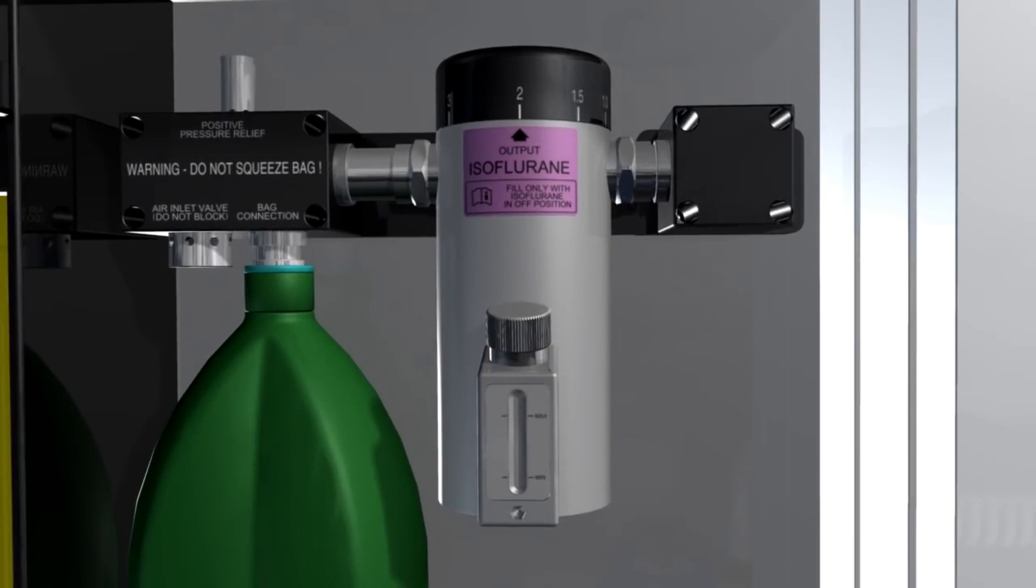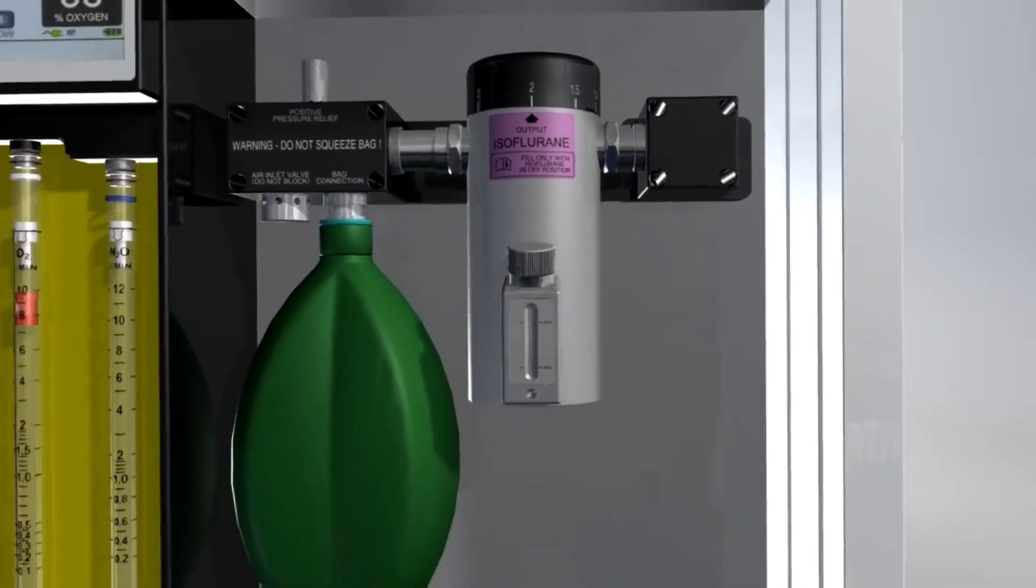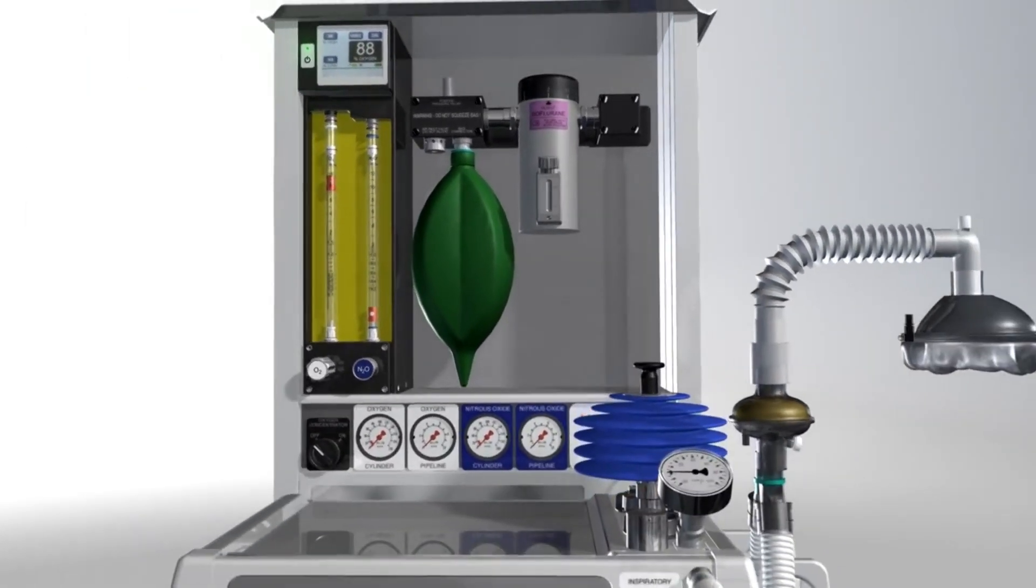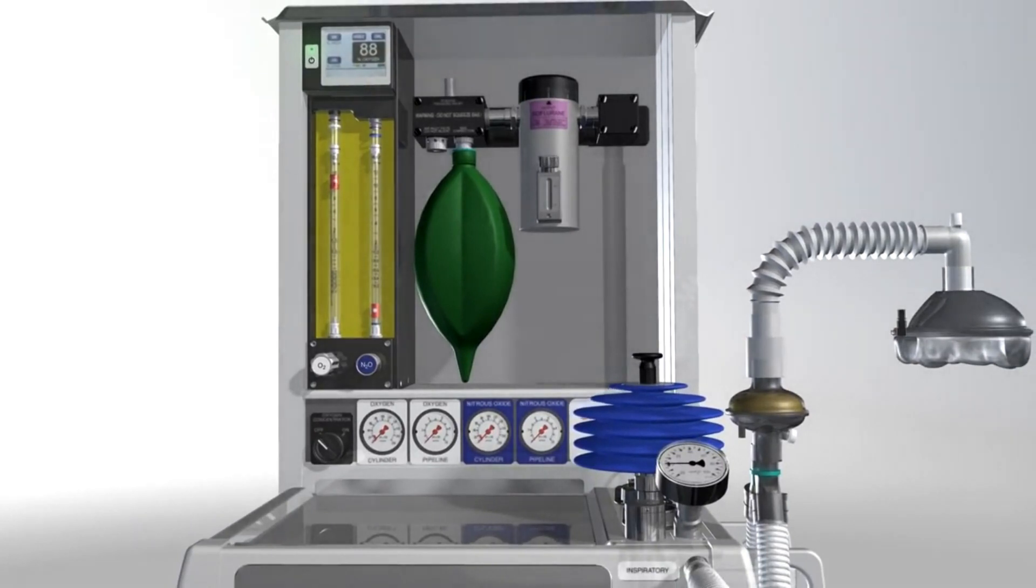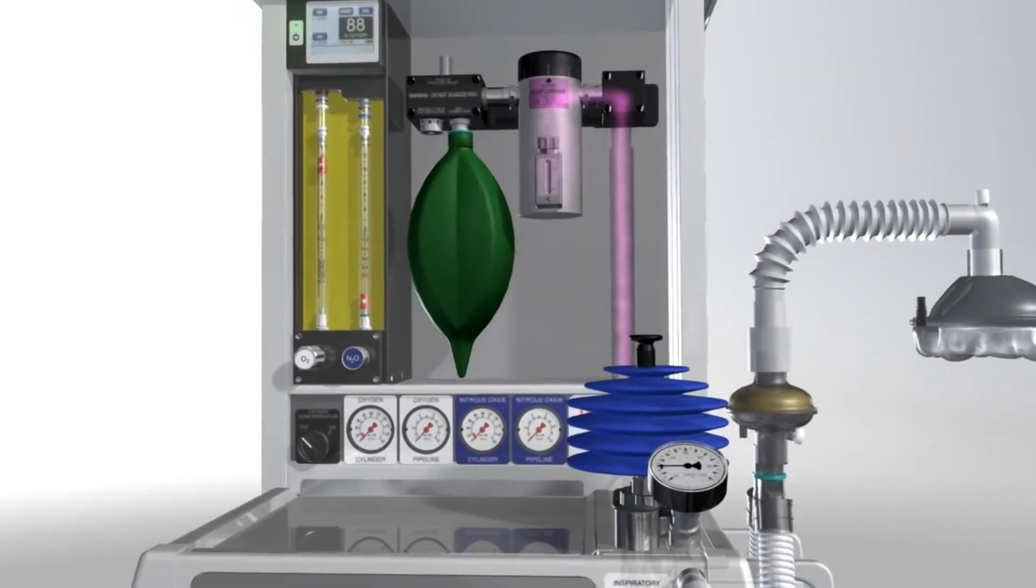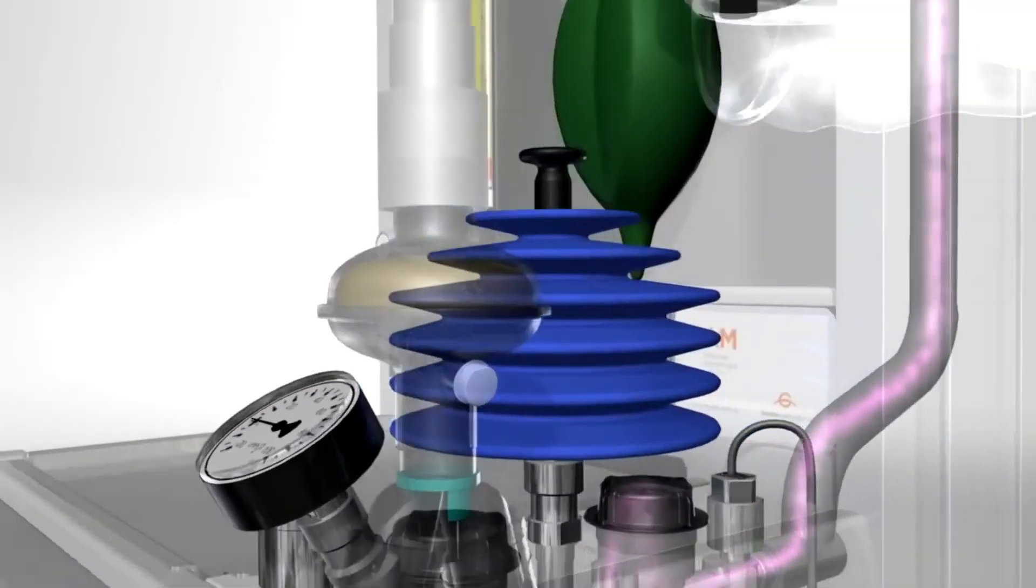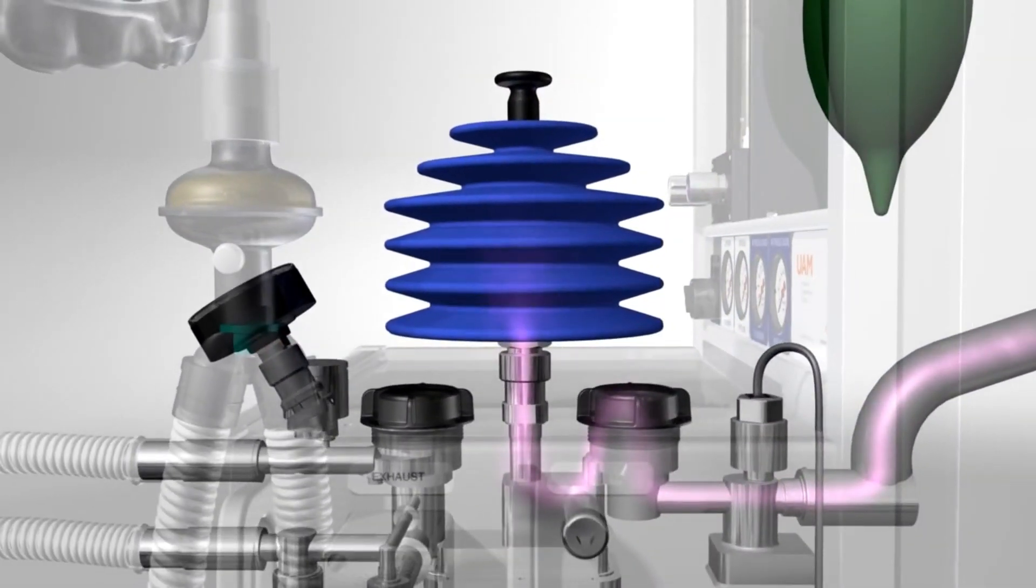The internal resistance of the vaporizer is usually high, but because the supply pressure is constant, the vaporizer can be accurately calibrated to deliver a precise concentration of volatile anesthetic vapor over a wide range of fresh gas flows.